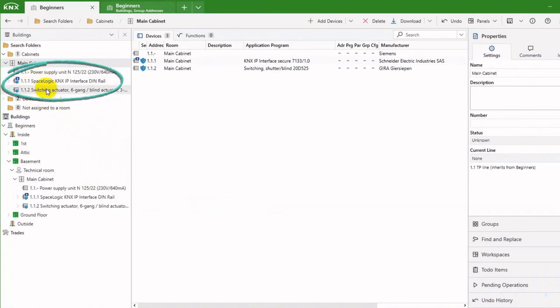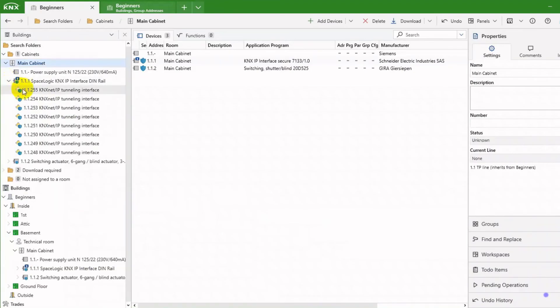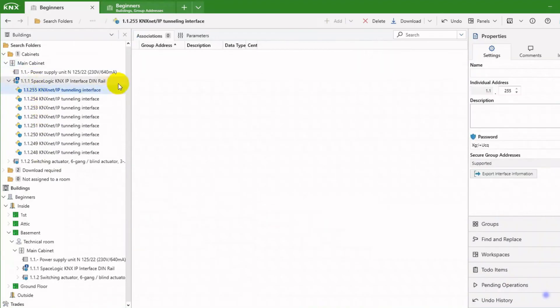The IP interface and the switch actuator get assigned an individual address automatically. The blue shield indicates KNX Secure is active. On the IP interface, I can see eight additional addresses. These are for IP tunneling interfaces, and I can associate group addresses here.